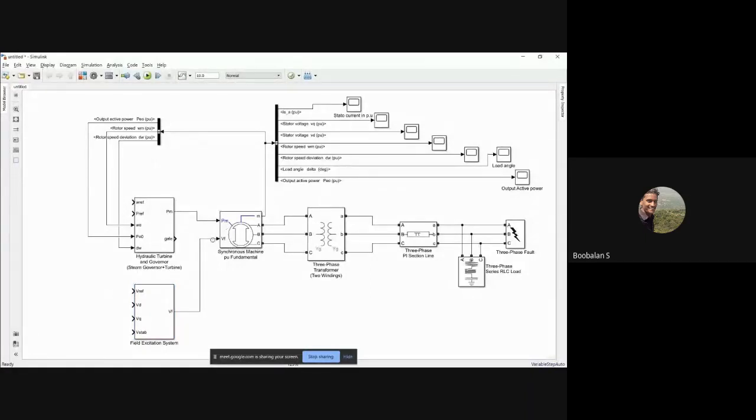There are two methods for controlling the load angle, maybe the torque angle, of my synchronous machine. One way is to adjust my turbine speed with the help of my servo motor amplification, which you can measure. It is going to control my steam governor with the help of the PID controller, which adjusts the steam flow rate, and you can maintain the constant frequency by maintaining constant speed.